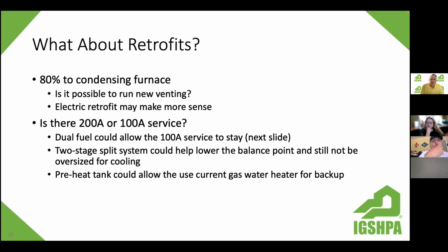Retrofits, of course, are important. That report we looked at earlier was on new construction, but suppose the customer wants a more efficient system. Well, if they go from an 80% furnace to a condensing gas furnace, are they going to be able to run that new venting? They've got to have outside intake. So they're going to have a way to get that outside air to the space. Even a concentric fitting might not always work in some cases, depending upon how it's vented. So an electric retrofit might make more sense than what it used to, especially with the prices of gas today.